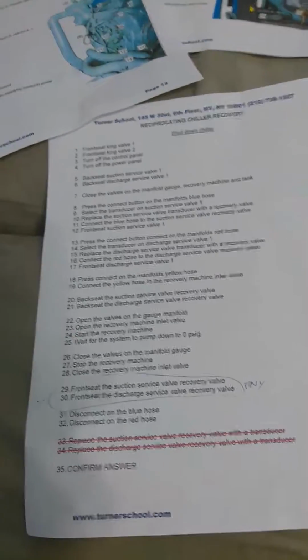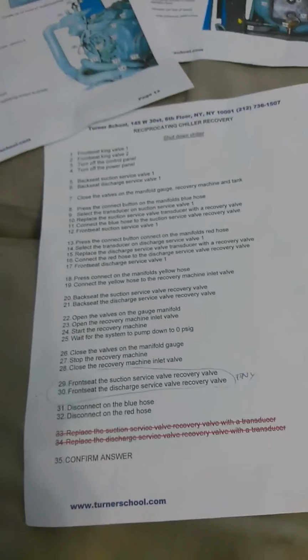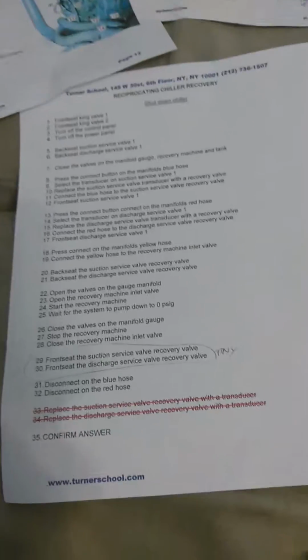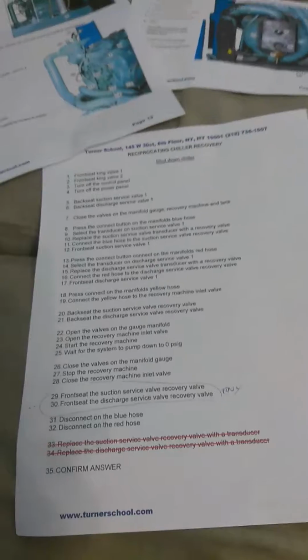Open the valves on the gauge manifold. Open the recovery machine inlet valve. Turn on the recovery machine. Wait for the system to pump down. Close the valves on the manifold.